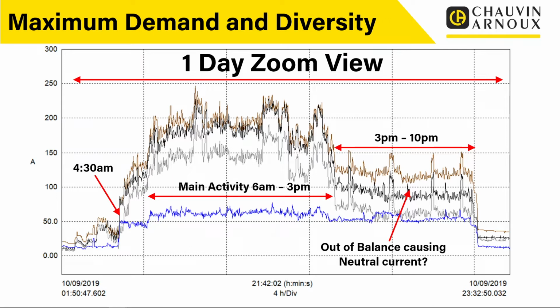And if you were going to add equipment onto this, you could then have a look and say, well, if I'm going to add a piece of equipment and it's going to come on at this time of day, it's going to add another 50 amps onto a certain phase, or it's going to be a 3-phase load. You can start to work out when you're doing additions and alterations what the impact of that would be. So you can see it's really powerful having these tools and being able to log what's going on over a period of time and then drill down and get the actual data. It's not just 100% of this, 50% of that, and a finger in the air job. You've got the proper data to back these things up, and you know that installation, when you design it, is going to be done right, and you've factored in everything that's going to occur reasonably within that installation, and you've also got the evidence to back that up as well.